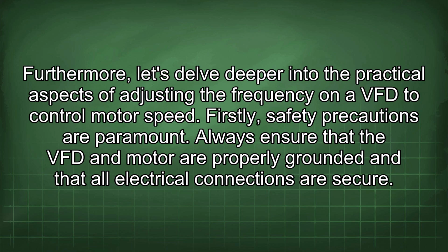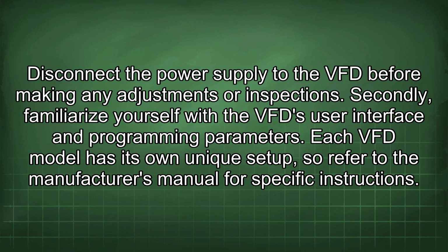Firstly, safety precautions are paramount. Always ensure that the VFD and motor are properly grounded and that all electrical connections are secure. Disconnect the power supply to the VFD before making any adjustments or inspections. Secondly, familiarize yourself with the VFD user interface and programming parameters. Each VFD model has its own unique setup, so refer to the manufacturer's manual for specific instructions.